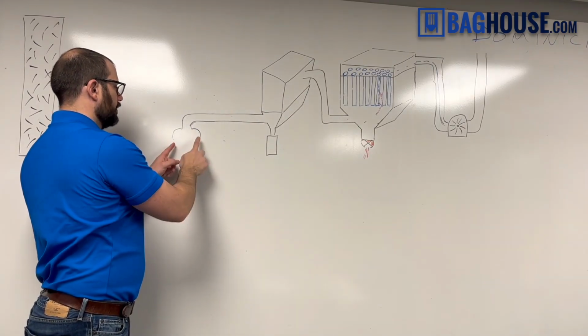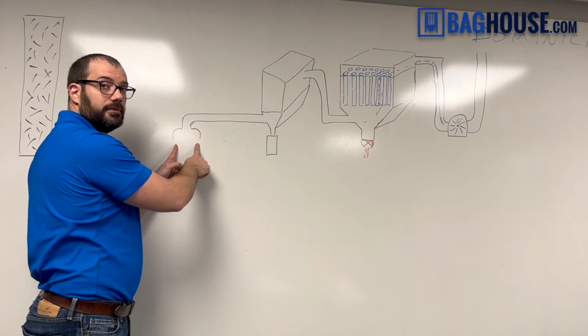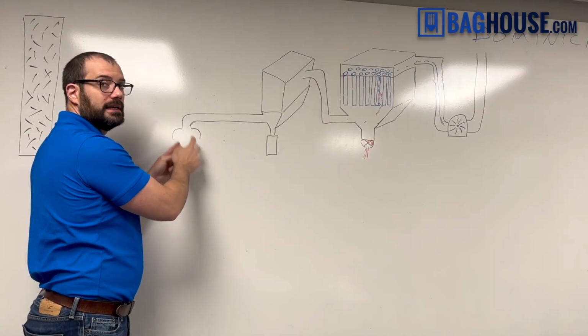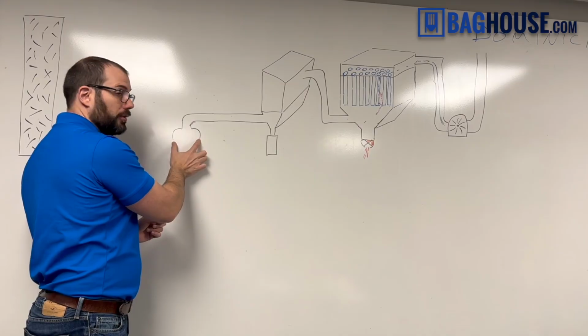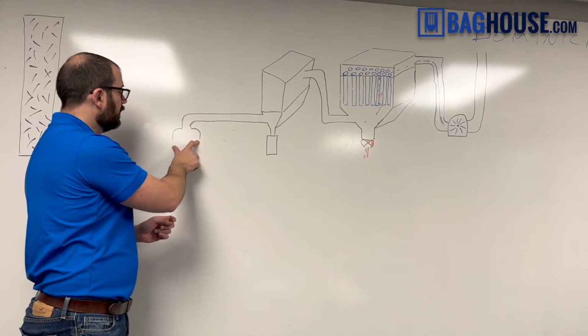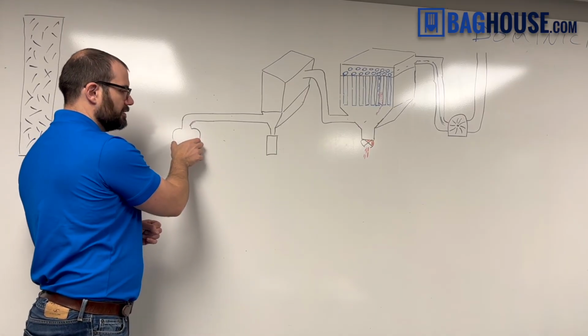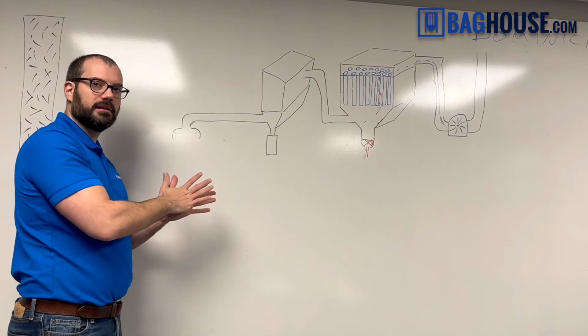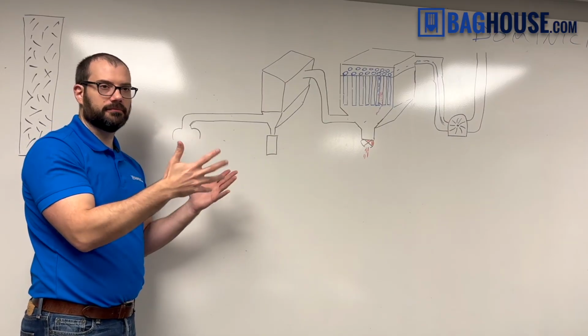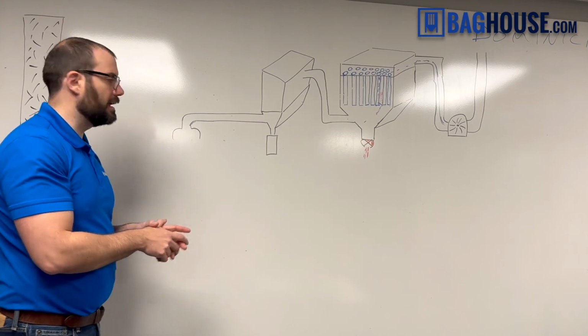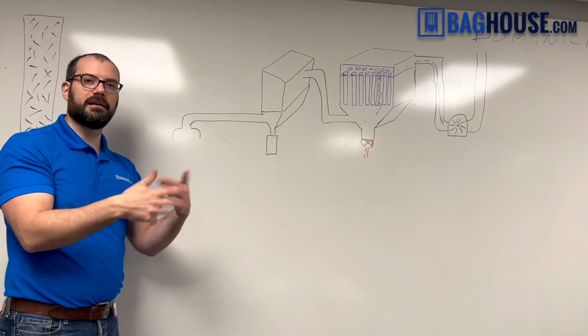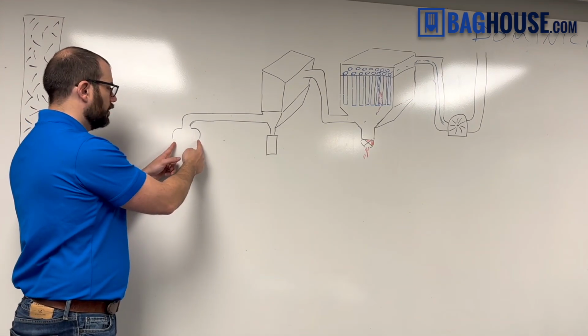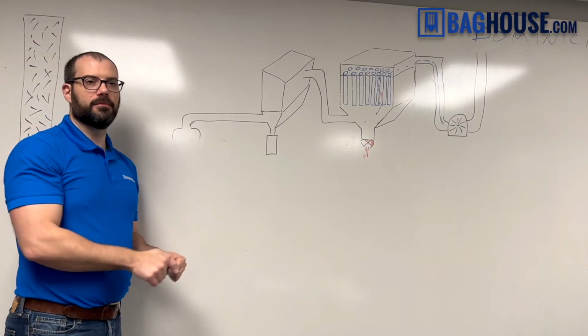It also includes the pickups, which is where we suck in the air. Sometimes the pickup hood is like you have in most places, and sometimes the pickup is directly connected, like a hard connection into the machine you're venting. Imagine you have a big box where they're grinding or cutting inside — sometimes you put the hood and it connects physically to the box.